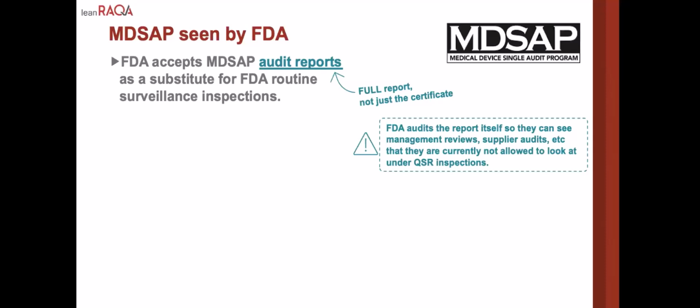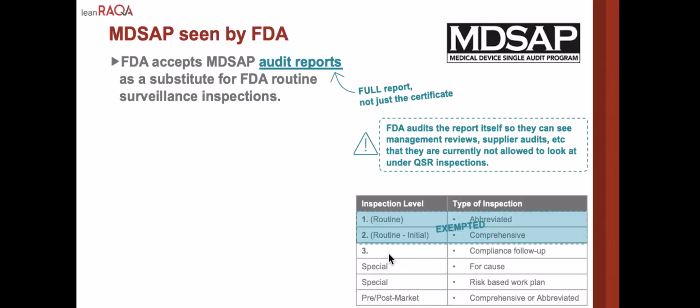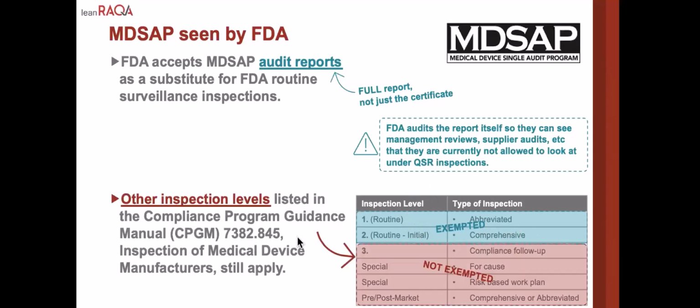Now, FDA doesn't consider risk-based necessarily based on anything that your company has said or done, but it can also be just the type of products that you make. Whether your products have been associated with any events or not, if it's a product that the FDA is paying attention to across the industry, they will say, well, this is risk-based, it's for cause, so we're not going to accept your MDSAP report, and we're going to come see you every year, every other year, whatever it is. So this is just showing you the types of inspections you can and cannot use it with.